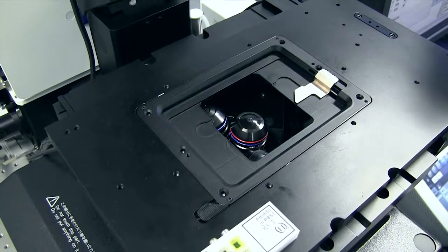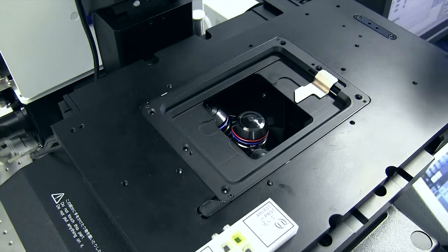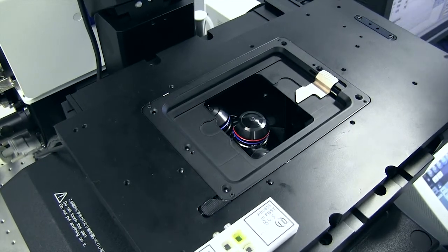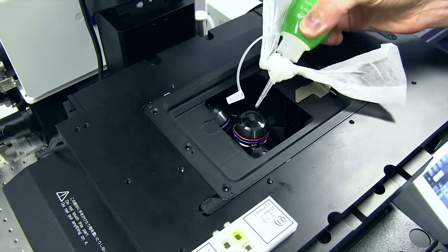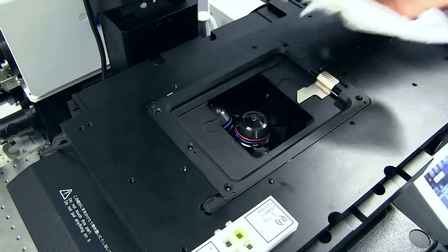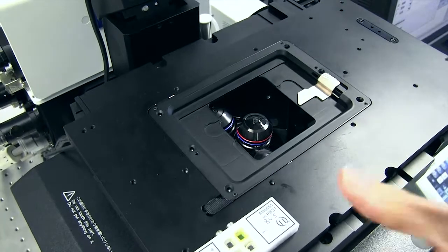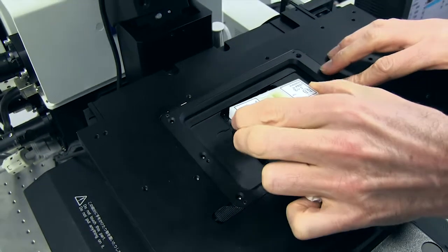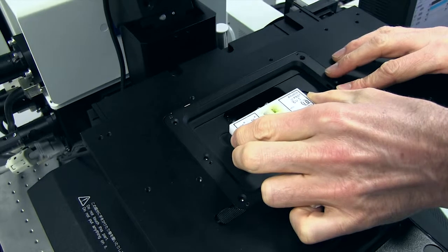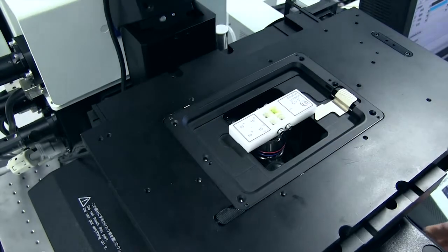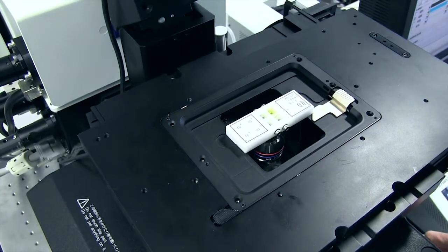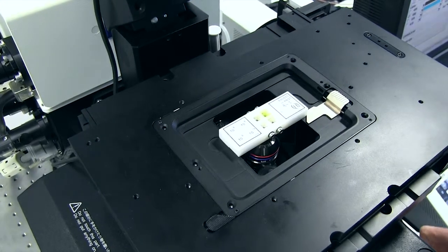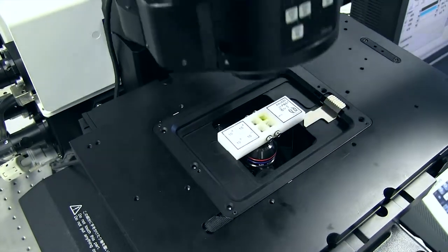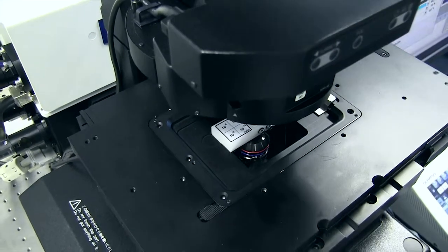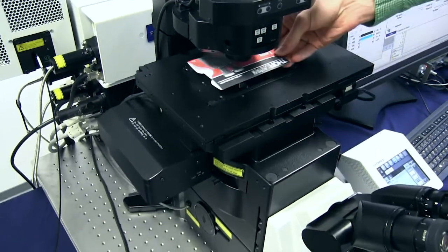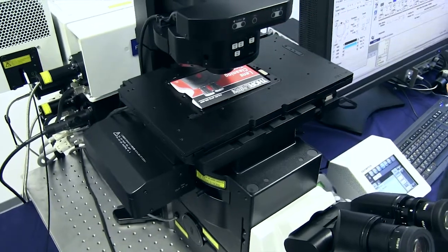FCS measurements require the use of high NA objectives. So in this case, we're using an Olympus silicon objective as an alternative to a water objective, and we place the sample onto its holder and move the stage to the right position. It is very important to cover the sample to protect it against room light.